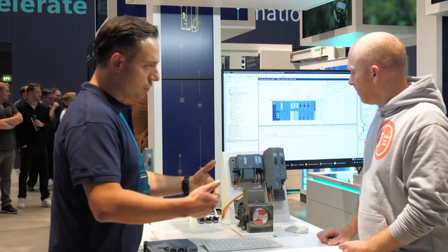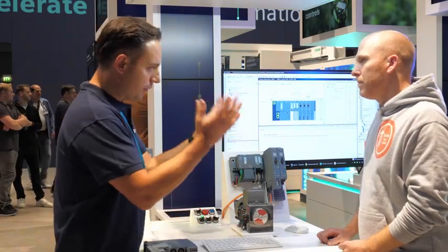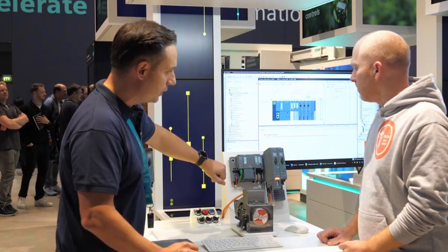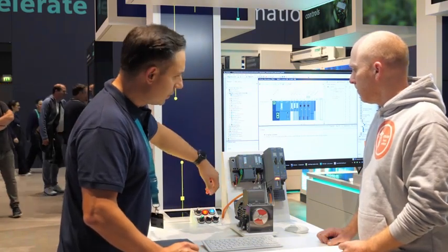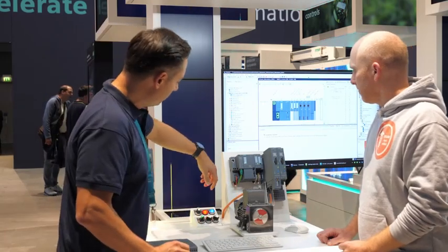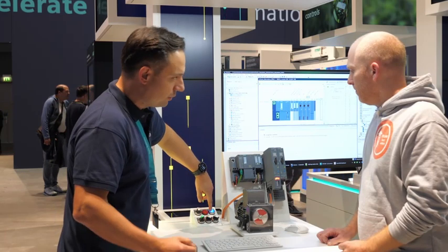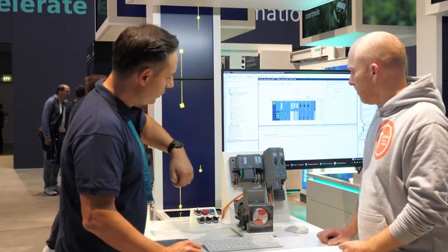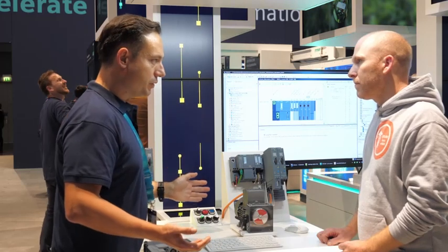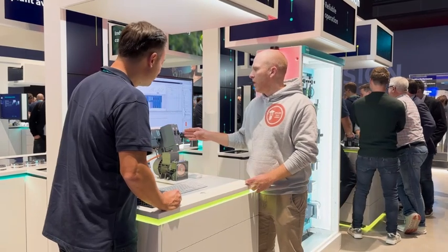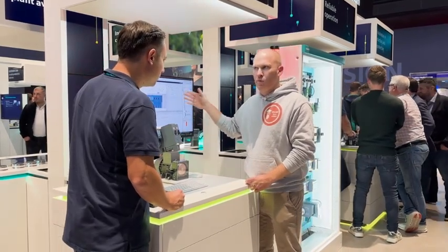So what you usually do in the facilities, you go there, you correct the cause of the short circuit, then take out the starting command because you don't want the motor to automatically start again. You do a reset either remotely or on the device. And now the application is ready to start again. So that's it.